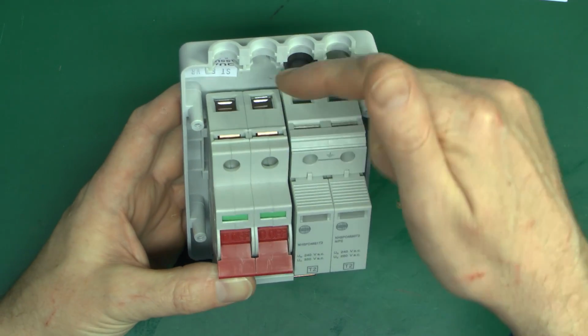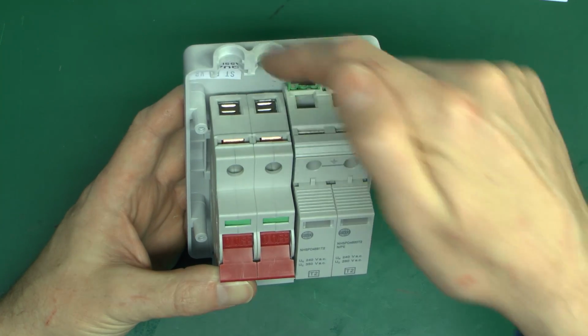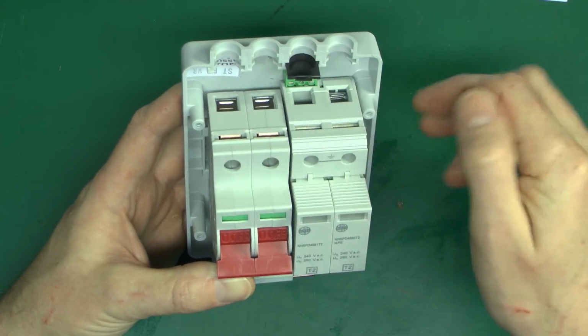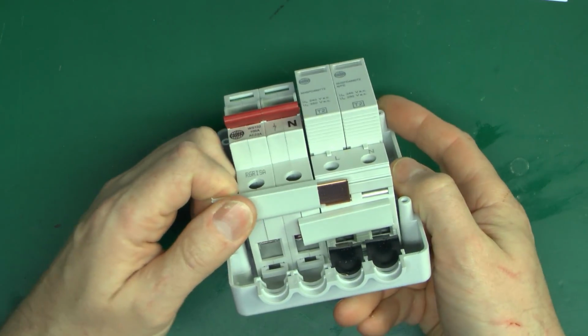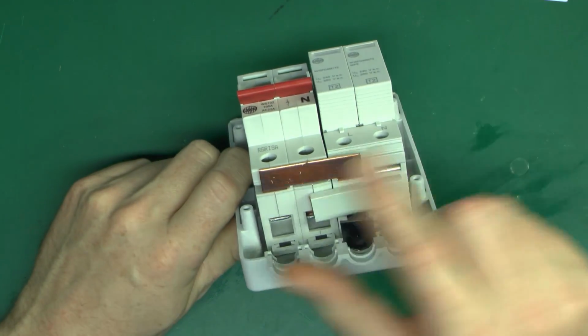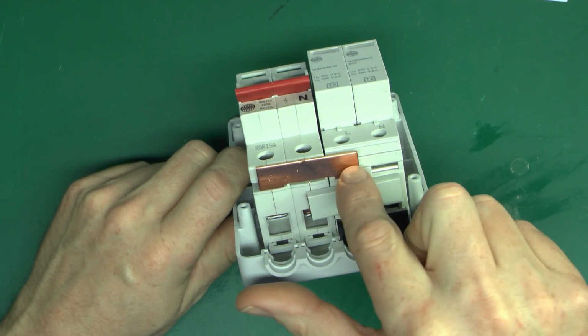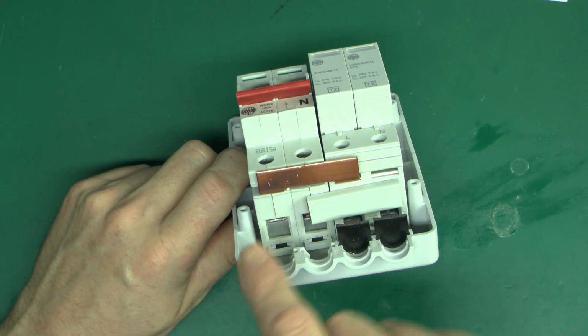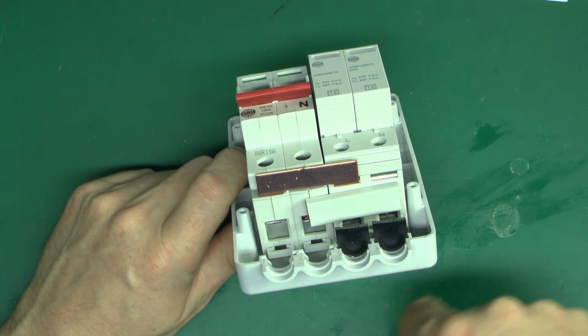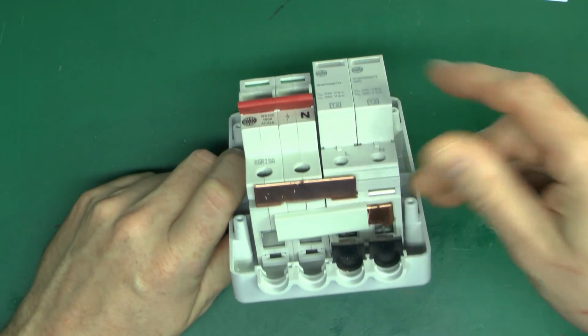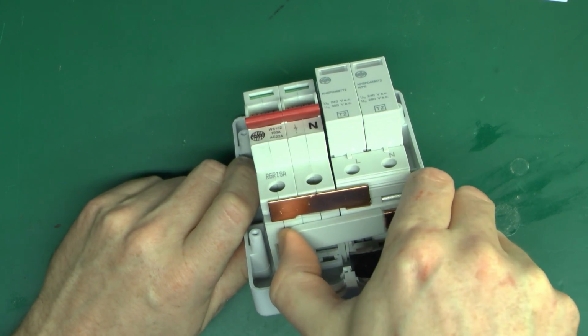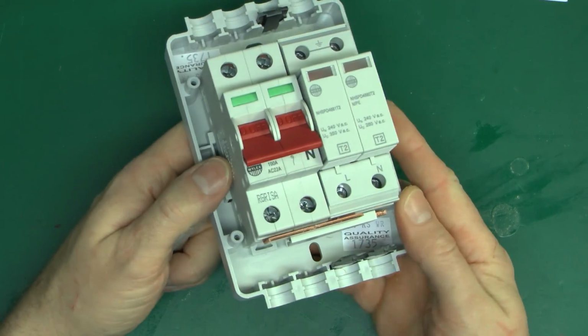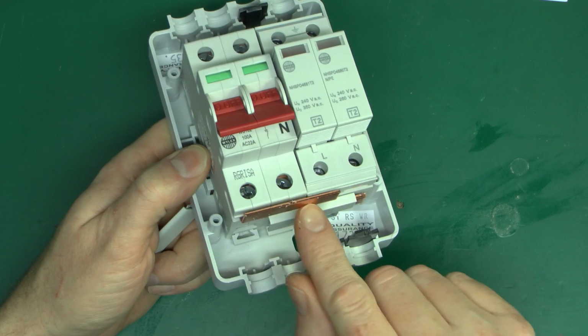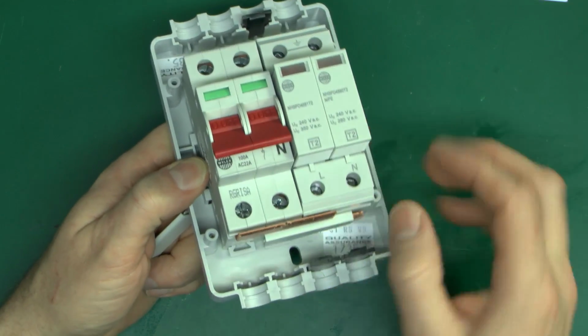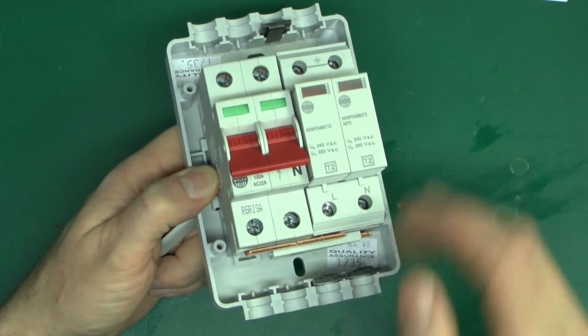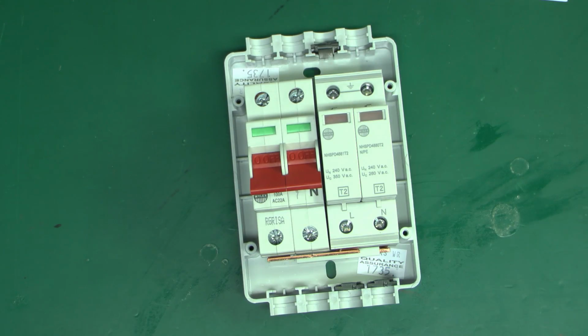So in the case of this one, the earth wiring is basically 0 distance as it's coming in and going out using the two terminals, and the length of the other is basically this piece of copper here. It's just basically between here and here. So again, that's only a few centimetres in length, keeping it as short as possible. And the other one there, pretty much the same. So that's really the ideal arrangement. So it's extremely short, pretty much as short as you can get it. And again, it's right on the wires there. They just continue straight through.